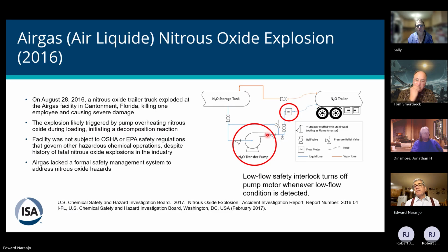If it falls below that certain flow rate, the pump is considered to run dry, and therefore you have the potential for a much higher temperature, which will evaporate the liquid, and you have therefore the potential for that liquid to escape, come into contact with some competent ignition source, and create an explosion.